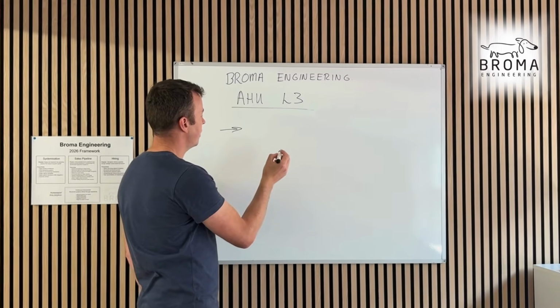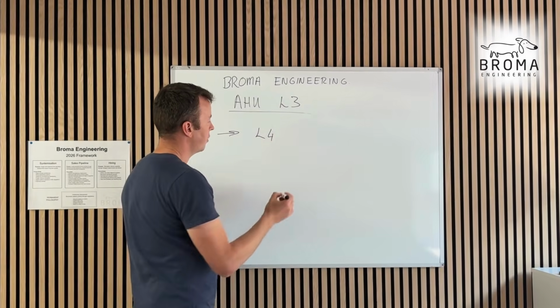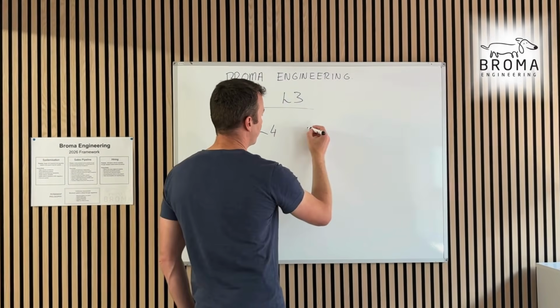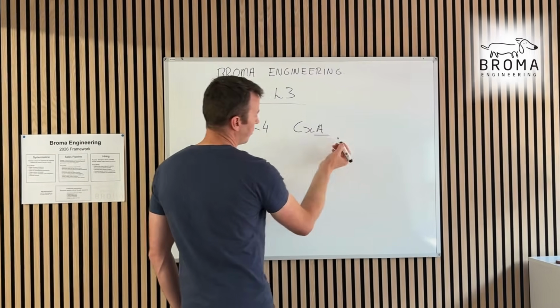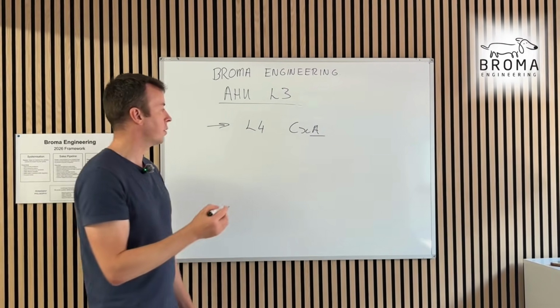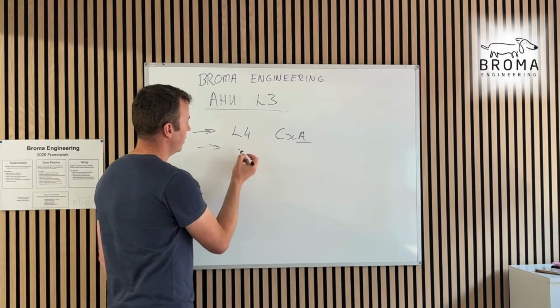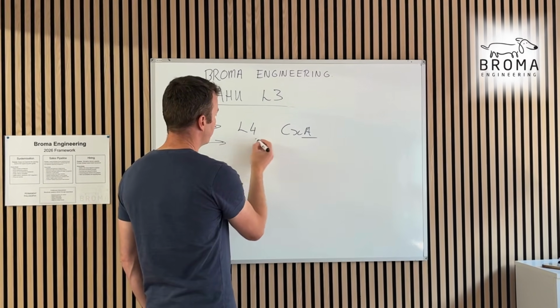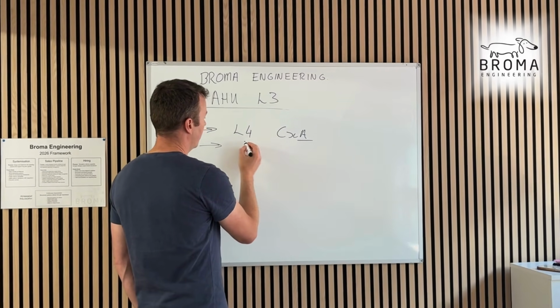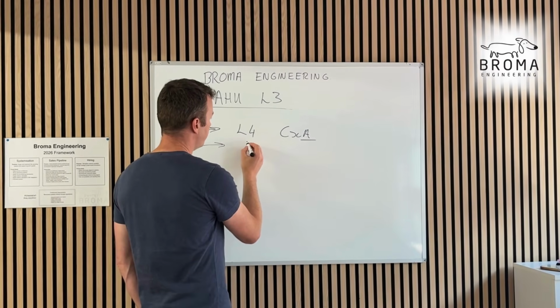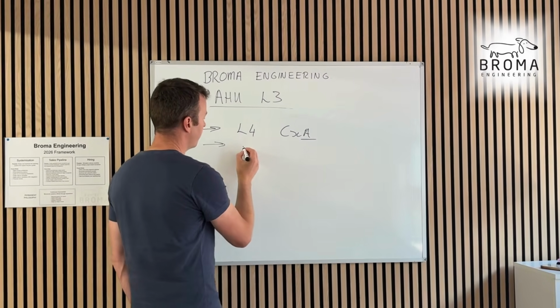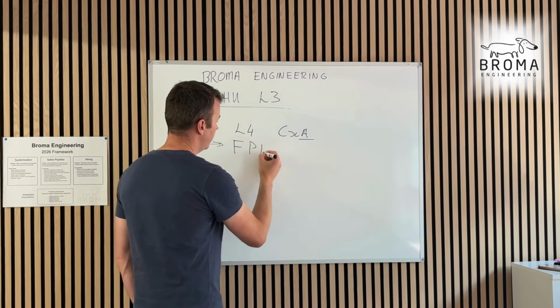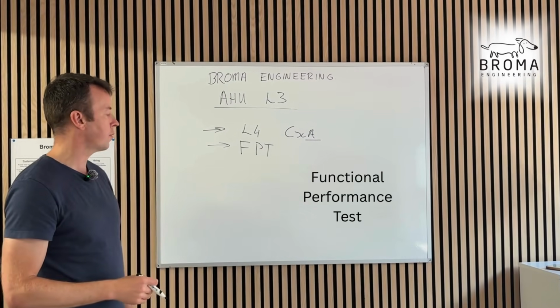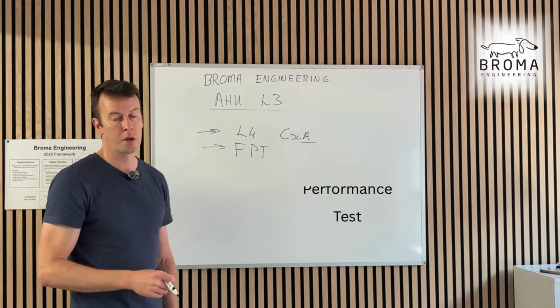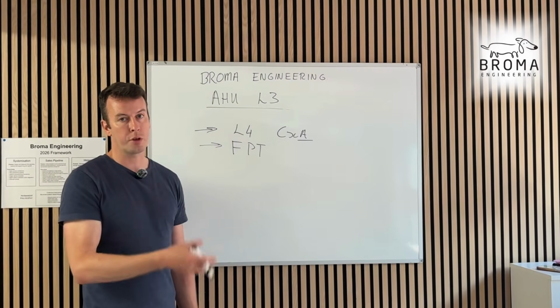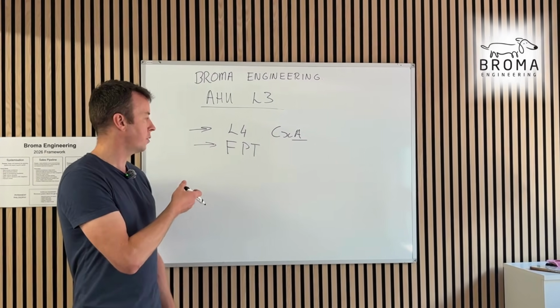Level 3 is complete, ready for level 4. Level 4 is third party, so it's the third party CXA - commissioning authority or commissioning agent. They're a third party coming in to basically redo level 3 scripts. They'll have their own scripts approved by the design team and the client, and they will run their level 4, called FPT, functional performance tests. They're making sure everything works the way it should as per design. They will need the SOO also, create scripts, get the scripts approved, run the scripts in the field.